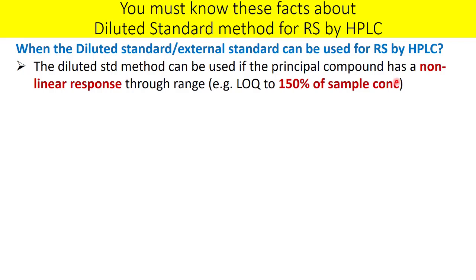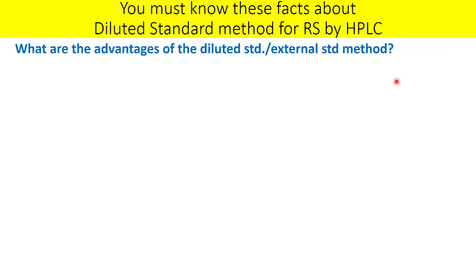Percent area normalization is another technique that can be used if you have a linear response from 4 ppm to 400 ppm or beyond. But if the response is not linear, use the diluted standard method instead.